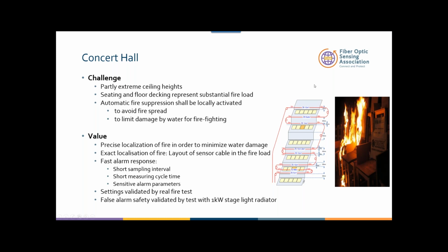Here's an example in the picture on the right, where you run the fiber optic linear detection, and then you can run in each one of those rows, and that's what we did. And the ability to pinpoint within the rows which seat is the one affected by fire is very important.